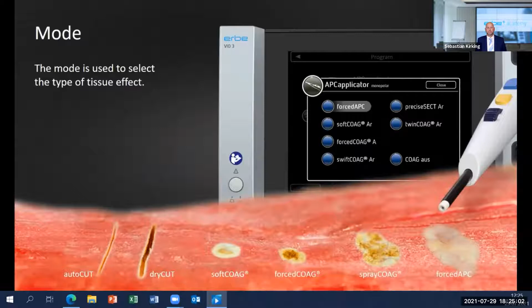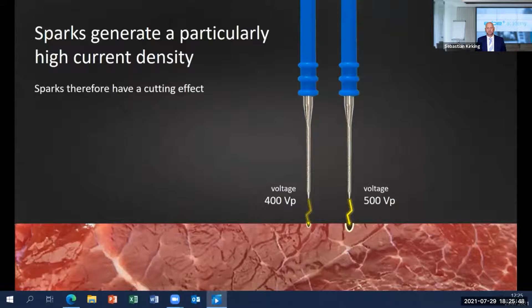When you look closely at the tip of an electrode, you will often see such sparks not only on spray coag and argon plasma coagulation. They actually play a very important role in electrosurgery for most monopolar modes. Because for cutting, the current density produced by the contact of the electrode is not even high enough. The required high temperature comes from these sparks that form when the voltage is somewhat higher than 200 volts. These sparks are like thousands of tiny, very thin needles, and they cause a very pinpointed vaporization of the tissue. This is actually where the cutting effect comes from. With even higher voltage, this effect becomes even stronger.